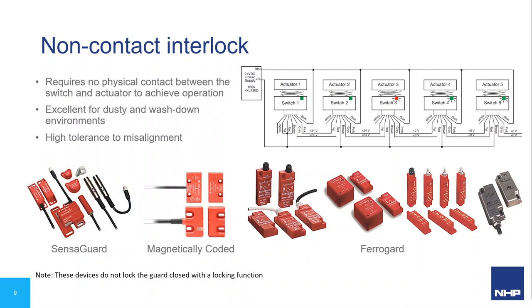The magnetically coded switches utilize reed contacts with a specially coated actuator, preventing defeat with a typical magnet because the actuator uses a specific series of north and south pole magnets unique to that switch. The Ferrogard family of non-contact switches are a more traditional magnetic reed contact style without coated magnets. The Ferrogard GD2 in particular is designed for the most arduous applications, featuring a full stainless steel housing for impact protection and the widest temperature range of any Ferrogard switch: minus 25°C up to 125°C.